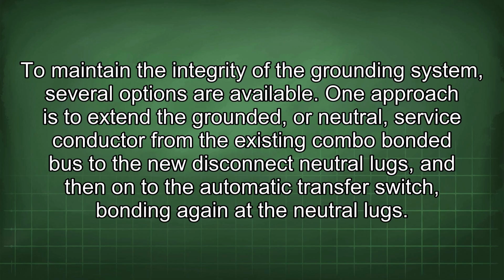To maintain the integrity of the grounding system, several options are available. One approach is to extend the grounded, or neutral, service conductor from the existing combo bonded bus to the new disconnect neutral lugs, and then on to the automatic transfer switch, bonding again at the neutral lugs.